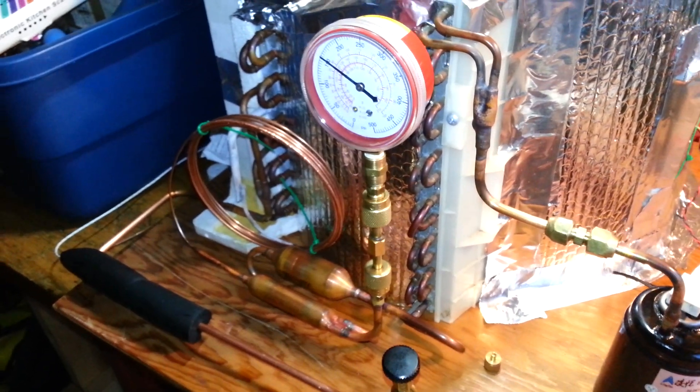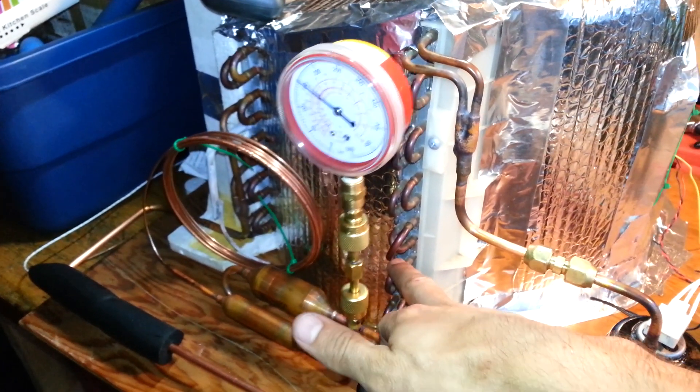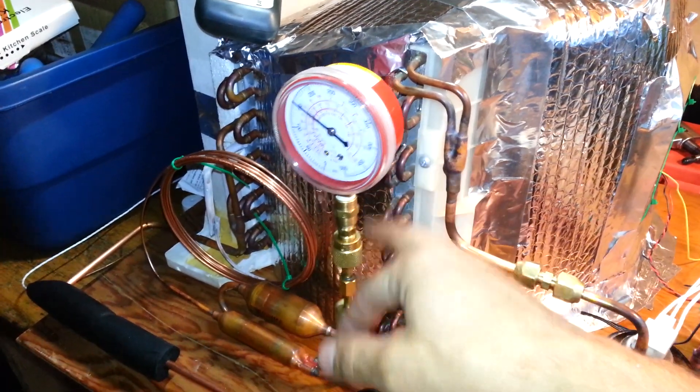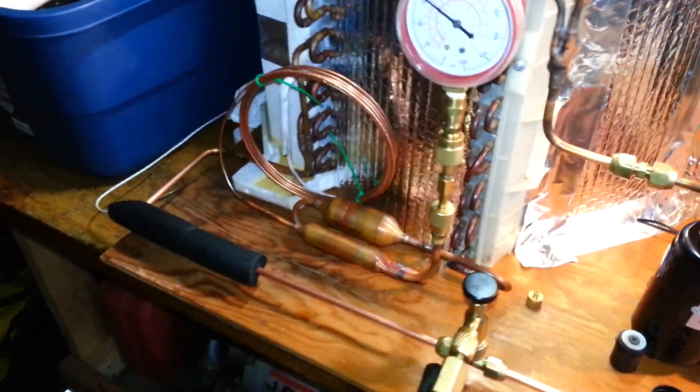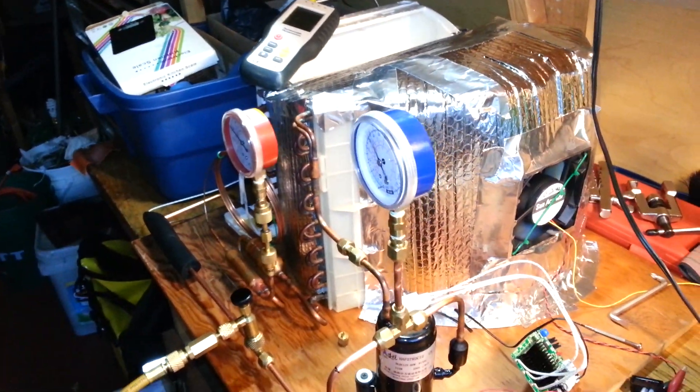Good sub-cooling, but it's far in excess. I probably wouldn't want to go anywhere beyond about this point as far as sub-cooling. I want to use as much condenser as I can to dump heat and to condense the high side.